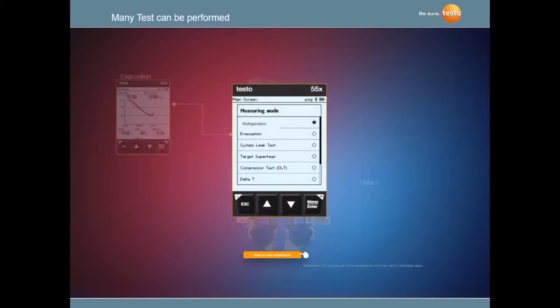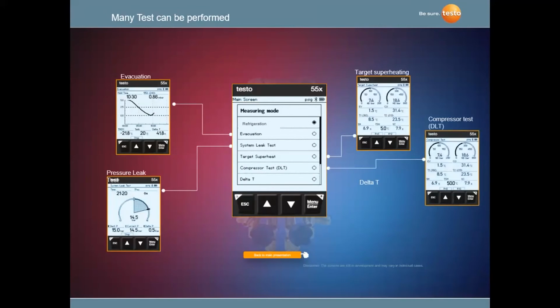Digital gauges, again, do a lot of different measurements, and this here happens to be the menu of a 550S, we call it. You'll see not only are you getting numbers, but you're also getting a graphic representation of what you're looking at. If you're looking at targeted superheat at the far right there, you'll see the simulated gauges. You'll see the numbers which represent the PSI in the system. You look at the evacuation screen, not only are you getting the micron measurement, but you're also getting a graph that shows the trending of microns when you're doing a vacuum. So you can set the target pull down at 500 microns. You can set the decay rate at 800 microns, and the instrument will alarm you. The cell phone will alarm you when you exceed those parameters.